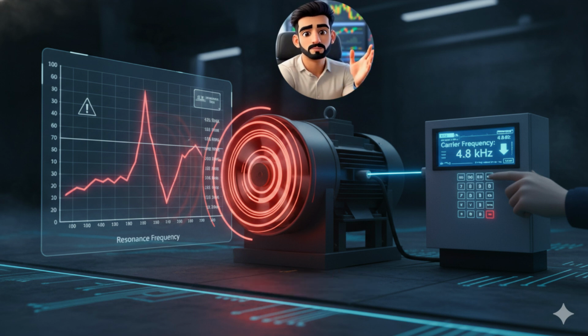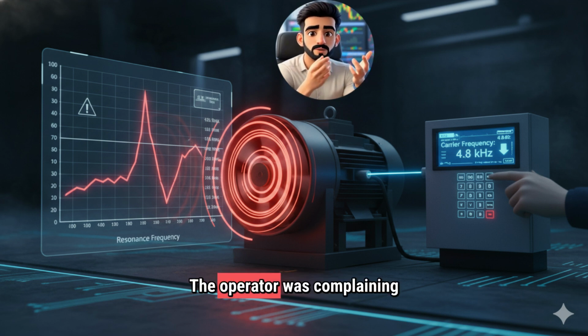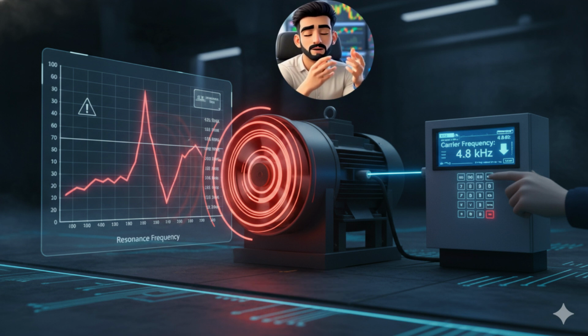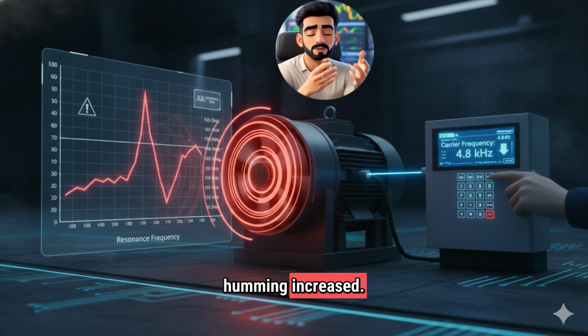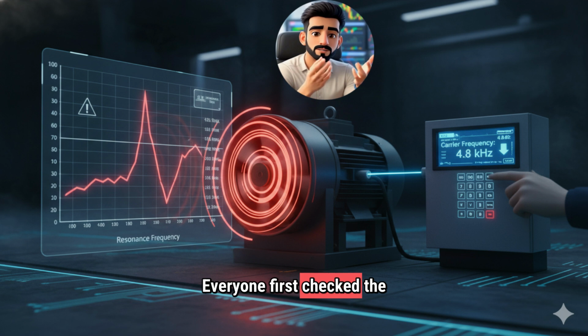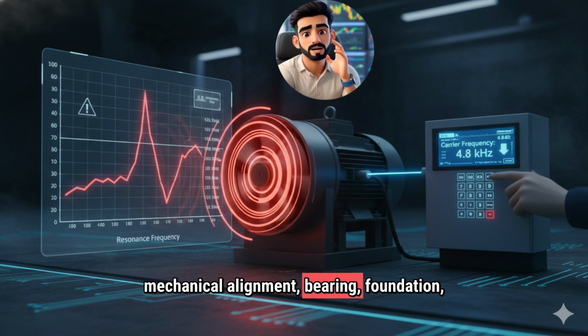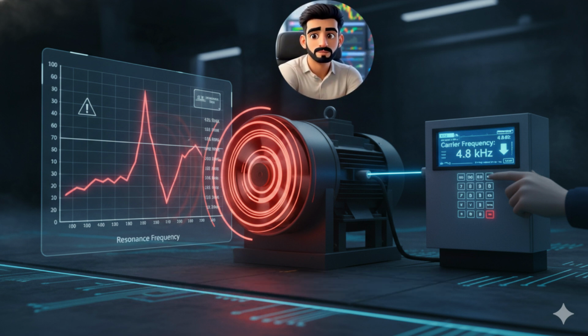The second case study was of a fan application. The operator was complaining that at high speed, the motor vibration and humming increased. Everyone first checked the mechanical alignment, bearing, foundation, and coupling. The mechanical side was found to be almost okay.